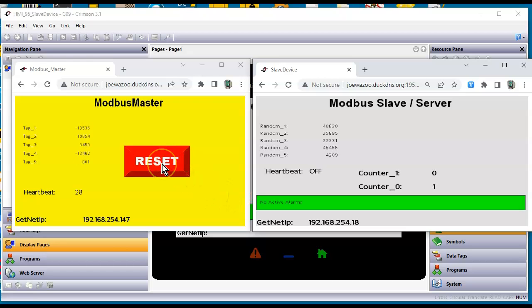So if I turn off the Modbus master or just disconnect the cable, I'll do a commit and reset here. I want you to notice what happens to the counter over here. After 5 seconds goes by, this thing of course keeps counting, but you notice the alarm: comms lost, stop the press. We've lost communications to the PLC master. Now this HMI is currently recycling power, and when it comes back up, watch what happens here.